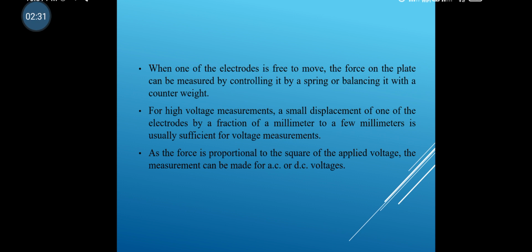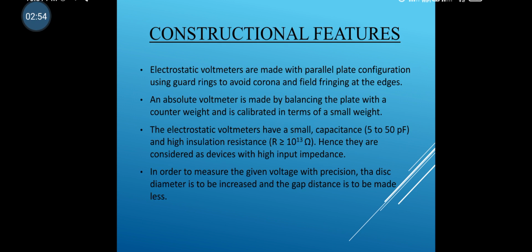For a high voltage measurement, a small displacement of one of the electrodes by a fraction of a millimeter to a few millimeters is usually sufficient. As the force is directly proportional to the square of the applied voltage, the measurement can be made for AC or DC voltages. We will see now the constructional features of the electrostatic voltmeter. So how exactly the electrostatic voltmeters are formed, we will see.